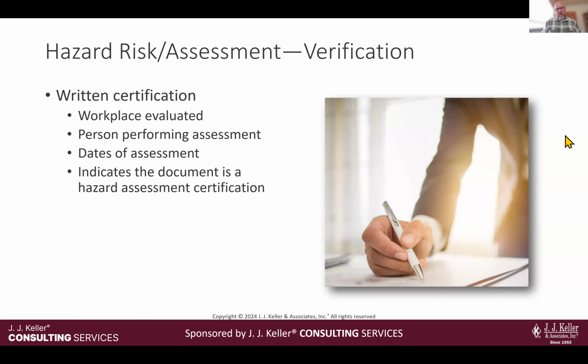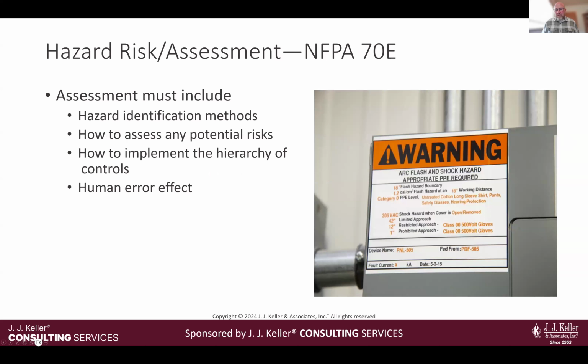When we get back to doing arc flash risk assessments, there are two ways. One is called the incident energy method, and the other is called the PPE categories method. The PPE categories method has been around for a very long time. It was developed maybe as a simplified approach, or that was the original intent, from my understanding of people I've talked to who may have been part of that conversation 20 years ago. It was designed to ease the burden of determining what PPE is required. But even after all these years, what I've found is that most people who tell me they use the categories method are telling me that to get themselves out of a jam, because it's a very uncomfortable conversation. They don't want to enter into that fray.